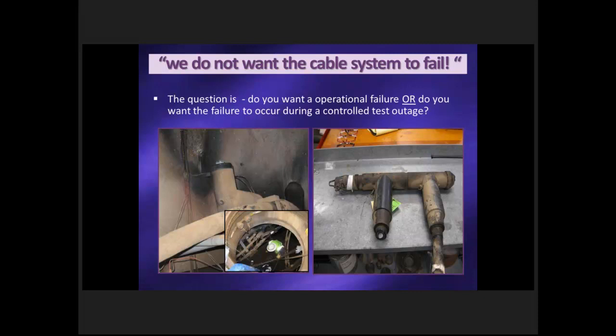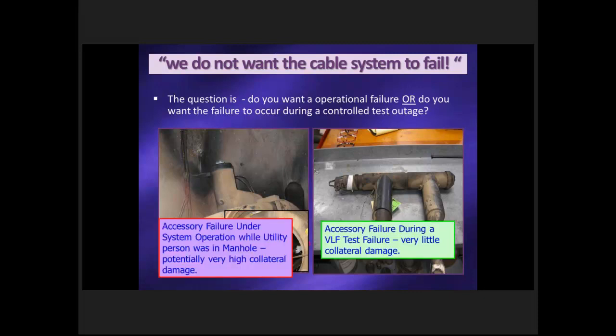You actually have to open it up before you see the damage, because you limit your current dramatically when you're doing offline type tests versus an online type of environment where anything does flow. Whatever the fault is, it can dramatically cause not only collateral damage to equipment but also potentially to people as well. So, two boxes there just highlighting what I've just gone over.